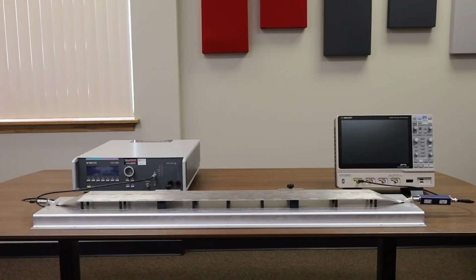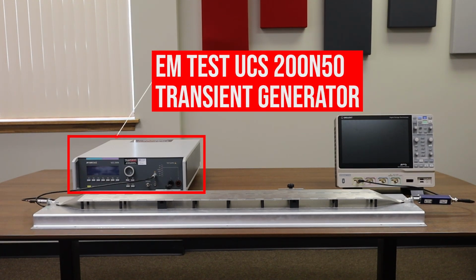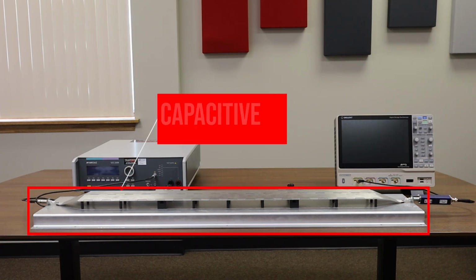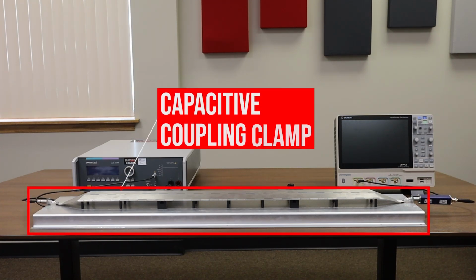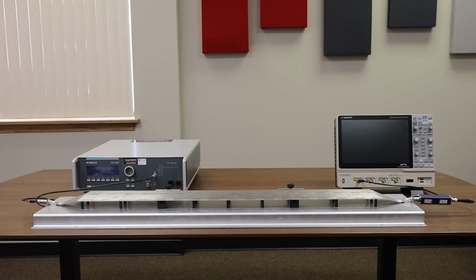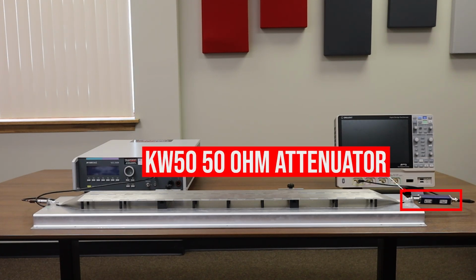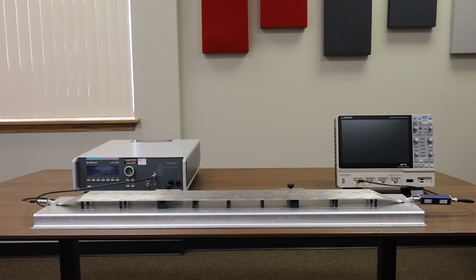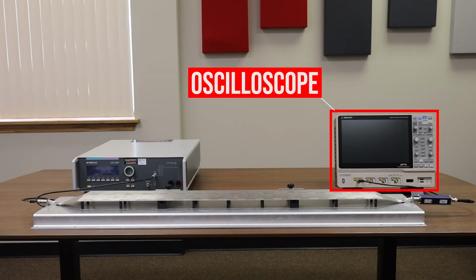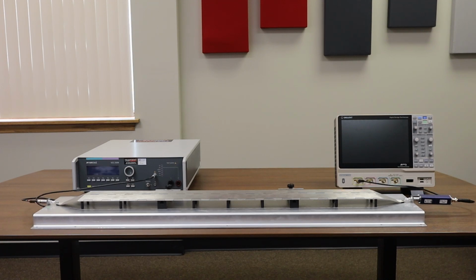Now we're looking at the transient pulse level adjustment in section 4.5.3. Let's start from the left and work our way right. On the far left, we have our UCS 200N generator, which is connected to our capacitive coupling clamp. On the right side of our capacitive coupling clamp, we have the KW50 50 ohm attenuator, which is connected on the opposite side, and then we have that attenuator connected to our oscilloscope. Once the pulse level adjustment has been completed, testing can begin.